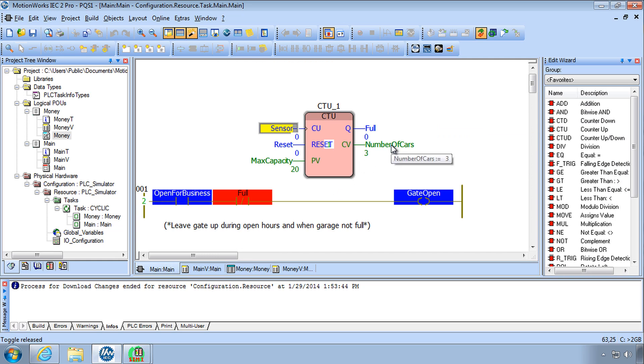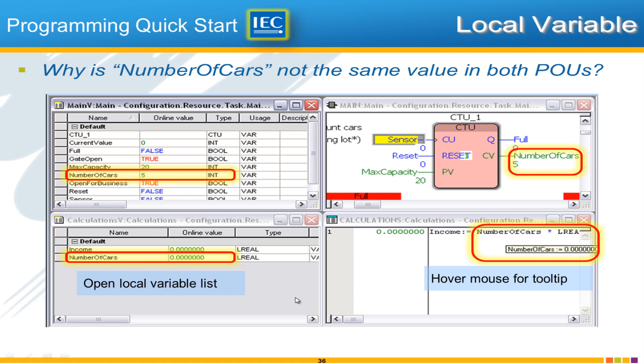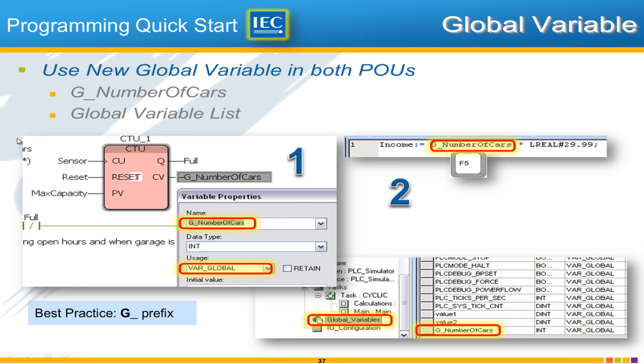Okay so now, now we got number of cars, two, three. All right I should be making tons of money over in the money POU. Wait a minute, it still says zero. I've got number of cars here says zero. Number of cars here says three. So what could be going on? And what's going on here is that number of cars is not the same value in both POUs because it's not the same variable. If you look at the variable list, you'll see that number of cars in the main POU is an integer data type and that number of cars is an LREAL, and it's just a completely separate variable. Each local variable list has its own variable. Now you can reuse the names of variables between the different POUs.